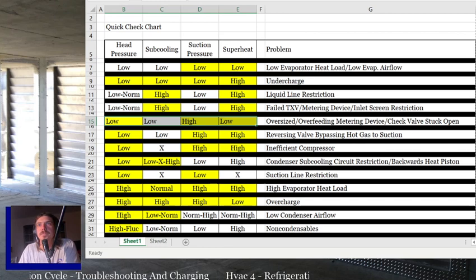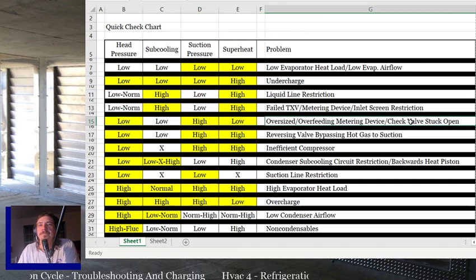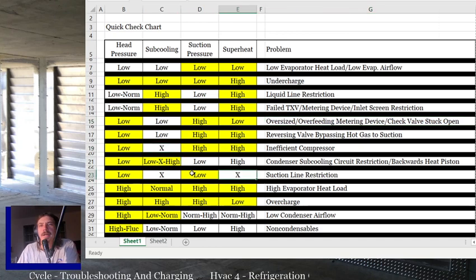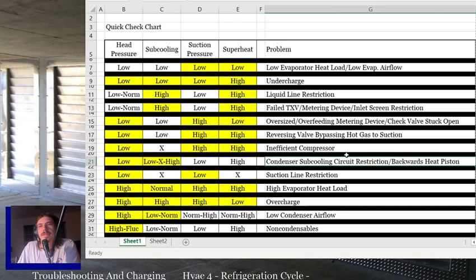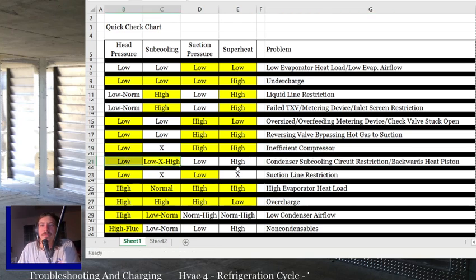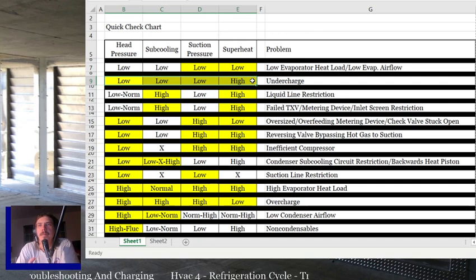The other reason it's there is because a lot of times the other values can be unreliable. And there are other instances where I highlighted it where it will be unreliable, but what I'm getting at is these X's mean that it doesn't really matter what values you get there, because the values you're reading don't really mean anything. It could look low, it could look high. It doesn't really matter because those readings could be anywhere. This one where it's low to high, it depends. But these two don't really matter when you've got these two together. So the condenser subcooling circuit restriction is kind of weird. When we talk about that, you'll get what I mean. But anyway, these highlighted values together are what make that combination whatever it is, essentially.